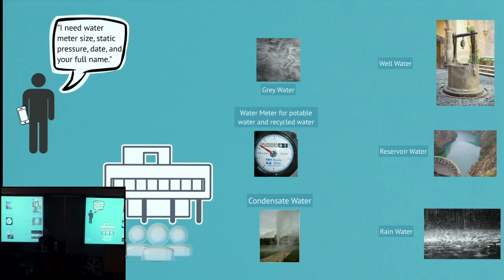Now, the first thing about water meters is that before you start your design, you will have called the water agency that is feeding your project, and you'll ask for the water meter size and the static pressure. Make sure that you put down the person's full name and the date, because when you go out into the field and check the water meter, it's not always possible to get the cover up. It's a concrete cover, and it takes a special tool for that. So you just have to rely on what the water agency told you.